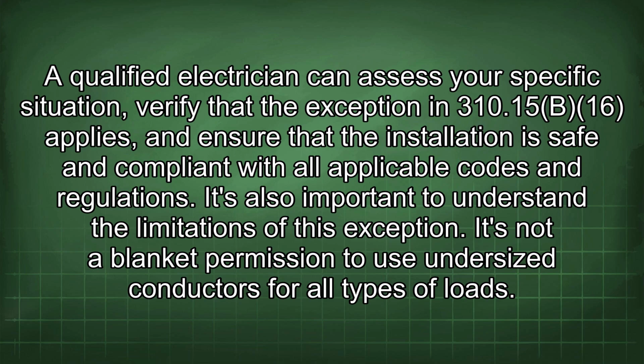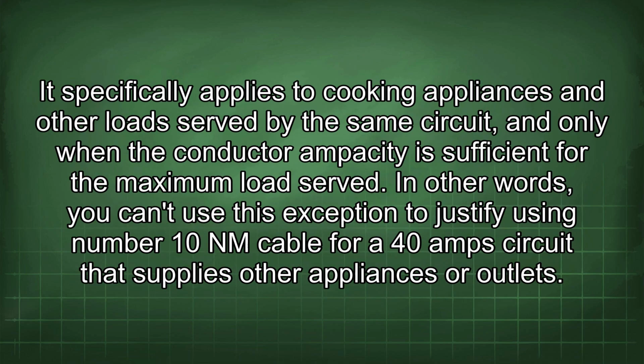It's also important to understand the limitations of this exception. It's not a blanket permission to use undersized conductors for all types of loads. It specifically applies to cooking appliances and other loads served by the same circuit, and only when the conductor ampacity is sufficient for the maximum load served. In other words, you can't use this exception to justify using number 10 NM cable for a 40 amp circuit that supplies other appliances or outlets.